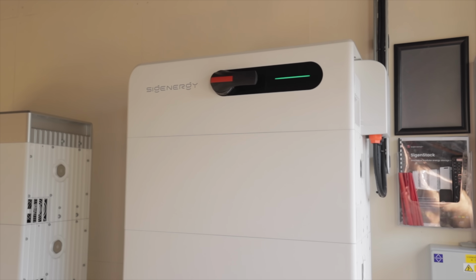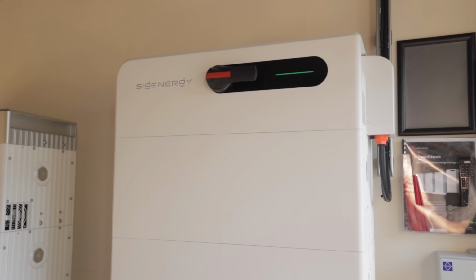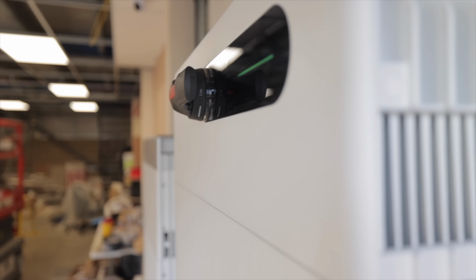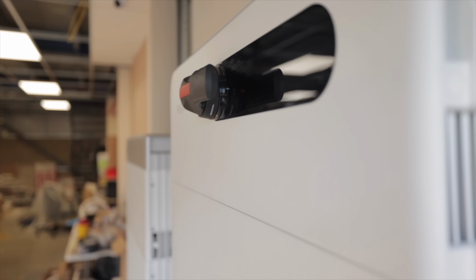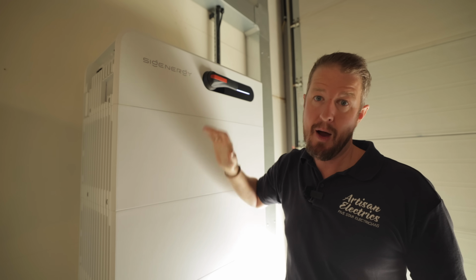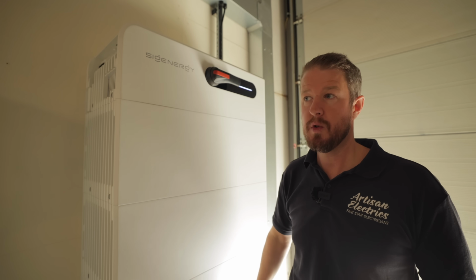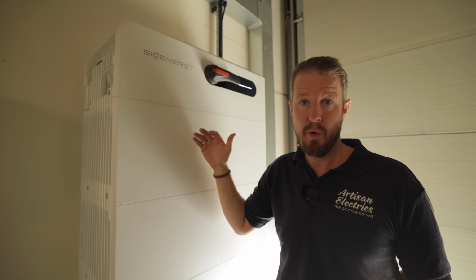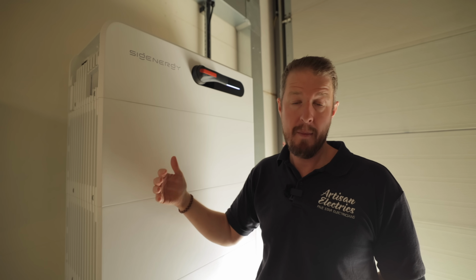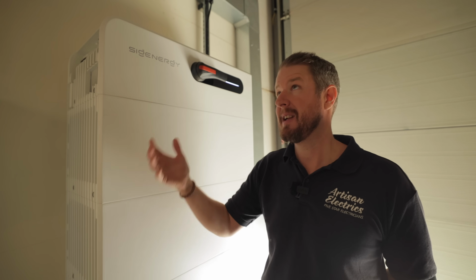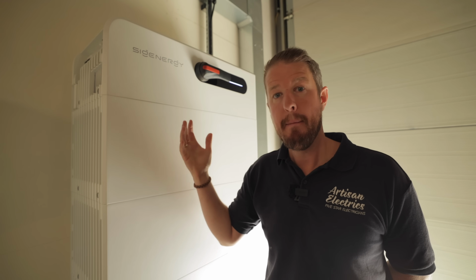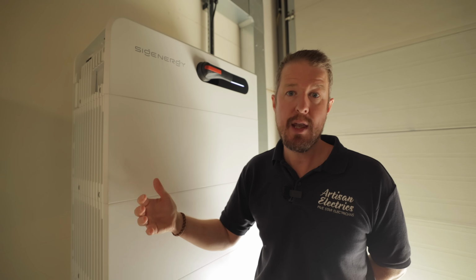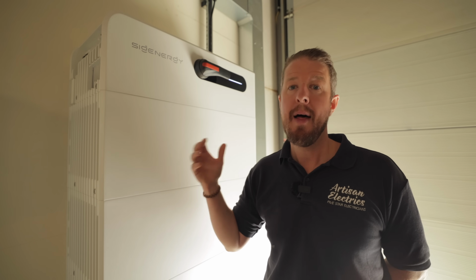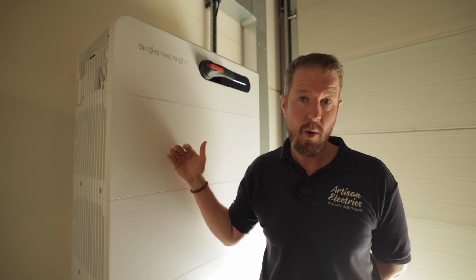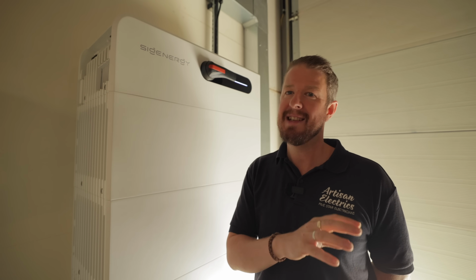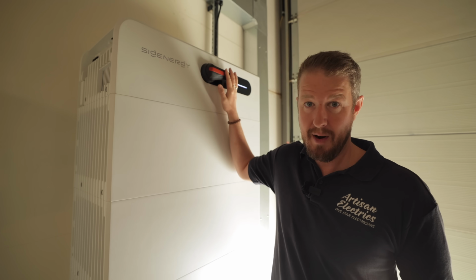Depending on what level of discharge you need will guide your selection when it comes to the battery controller. The one that we've selected here is the M2 0.5C BST. That allows a half C discharge, so with 120 kilowatt hours of battery storage, we can discharge at 60 kilowatt peak, which is more than enough for us, especially considering we've got a 60 kilowatt inverter. But if you needed a higher discharge rate, you could go with the 1C battery controller. That would allow you to discharge 120 kilowatt from these batteries. And it's important as part of the design phase that you make sure you select the correct battery controller.